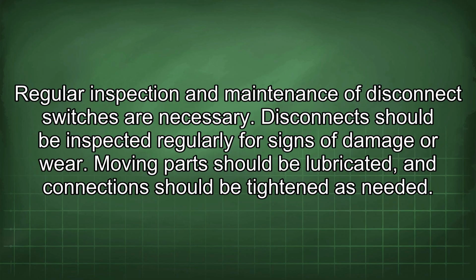Regular inspection and maintenance of disconnect switches are necessary. Disconnects should be inspected regularly for signs of damage or wear. Moving parts should be lubricated, and connections should be tightened as needed.